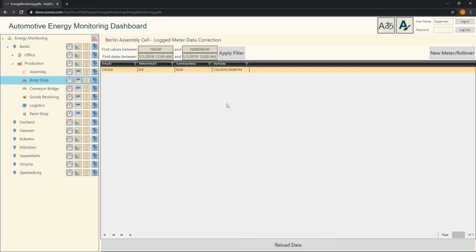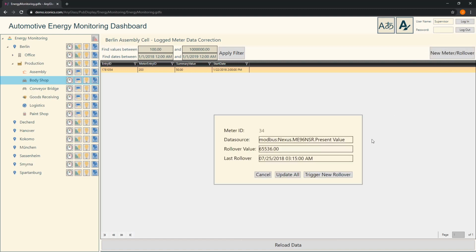Second thing to make aware of on this is that we also included a capability for triggering rollovers. Not uncommon thing with energy meters is that if they are serviced or recalibrated, it may reset the total consumption aggregate value for that meter. So to accommodate that, there's an ability within the system to define specific intervals where there was a known servicing by a technician of the meter.